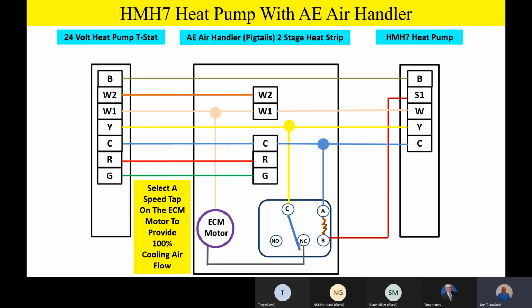Now, we always want to set our airflow up to 400 CFM per ton. That's our nominal airflow, 400 CFM per ton of cooling capacity. So if I've got a 3-ton unit sitting outside, on this normally closed contact we're going to want to select a speed tap on that motor that's going to give us 1200 CFM. If we have a 2-ton unit sitting outside, we're going to have it set on 800 CFM, and so on. So our initial airflow setting should always be 400 CFM per ton at 100% airflow. So if we've got a 3-ton unit outside, we want to make sure we have 1200 CFM on that 100% cooling airflow tap, whichever one we select. That goes to the normally closed contact on the relay.